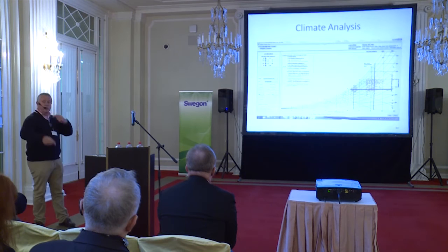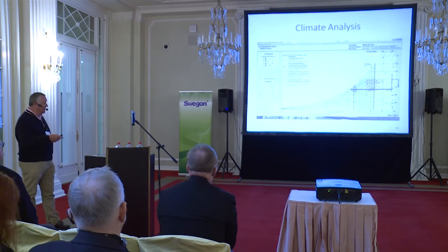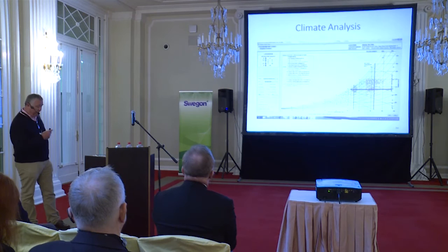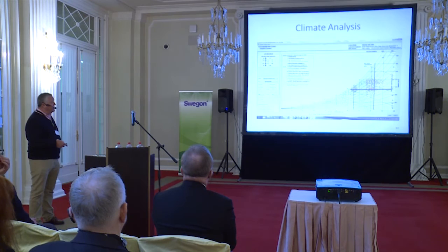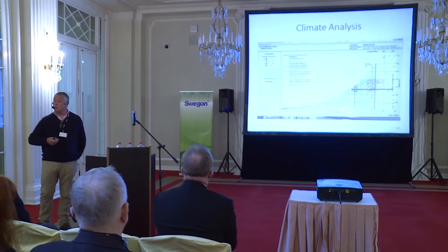I should have turned this around to get a Mollier diagram, but this is a carrier chart—just hold it up to the mirror backwards. So if we look at the number of hours for this particular place, this is Atlanta, Georgia, fairly humid. What we say is that anything above that line cannot be considered, because that air is too moist to go into the space. So it's not all those hours; we have to look at it properly.